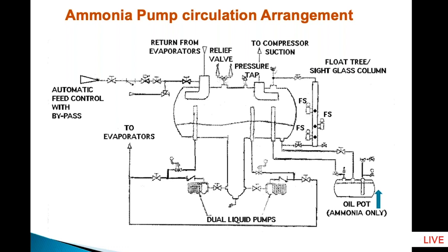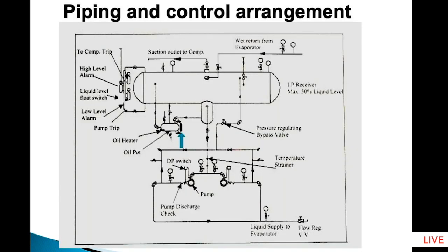So these LP systems are very important, very popular, and they are used in most of the ammonia plants which are low temperature, below minus 20 degrees centigrade, and large capacity plants where there are many air coolers or the process side equipment like blast freezer, IQFs, etc. is much away, about 50 meters, 60 meters from the plant room. So if you use gravity cooling, then the suction gas will get superheated. Therefore, it is recommended to use an LP vessel, because the LP vessel is kept inside the machine room in a closed loop refrigeration system. As I mentioned, there can be an independent lecture of 1 hour only on LP vessel design.